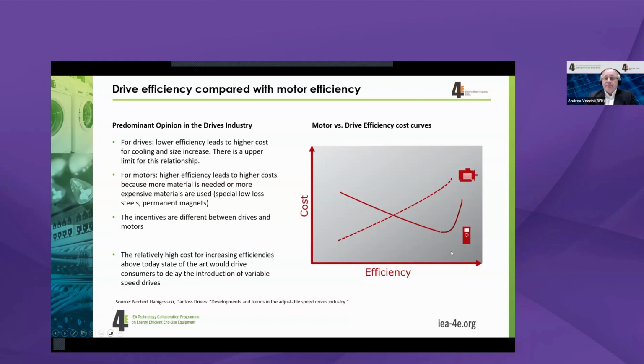So we reach about 97.5% efficiency with the drives at minimum cost, and there is a steep incline in cost if you want to reach only a small amount of higher efficiency. Whereas with motors, for example, you can get more efficiency gains with less cost, given by the smaller inclination of this curve. This has been a long-time argument, which, with the decrease of costs for silicon carbide and the additional benefit of cost savings which can be realized with silicon carbide in the auxiliaries as well as the filters, input or output, is getting less and less traction.